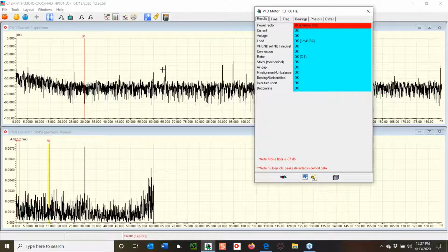So here we are in the analysis part. First thing that happens when I'm done collecting is it pops this up and it'll give me what it thinks. I can do a couple of things - I can ask it to take a look and verify the running speed and the pole pass frequency on its own.